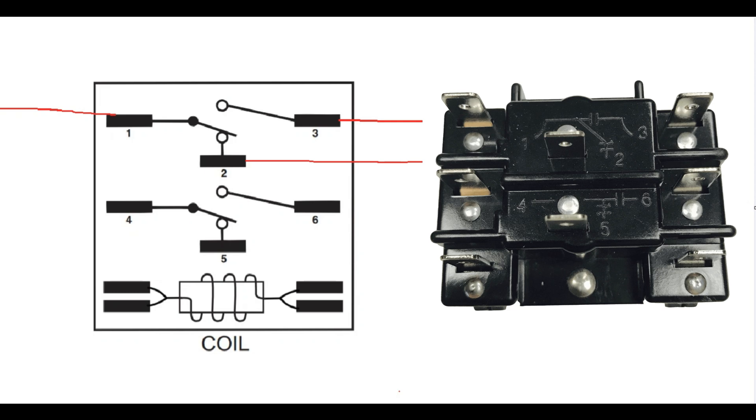So if we were to take a multimeter and check for continuity between one and three, we would get nothing. If we checked again between one and two, we would have continuity because that switch is normally closed.